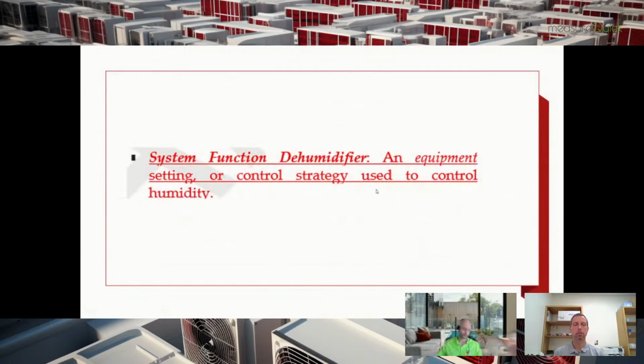There's a lot of conversation going on in our industry right now about the use of reheat dehumidification. In commercial, reheat dehumidification a lot of times ends up being a gas fired heat that is injected into the airstream to dry it out. In residential HVAC, this ends up being heat strips that are activated. So you've got to be real careful about the amount of power that you're using with this methodology, and you have to start thinking, is this a really good strategy to use in the shoulder seasons when you're not running your HVAC at all, but you still need to dehumidify the space and maintain a relative humidity set point? Is this really the best way to go?